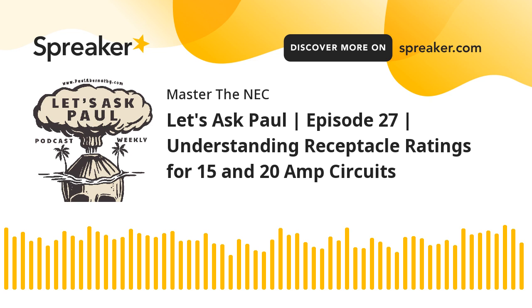So let's look at the very first one. Okay, so the very first thing we're dealing with is a 15 amp circuit breaker. Okay, it could be a fuse, but we'll say probably more modern homes are dealing in circuit breakers. So it's a 15 amp circuit breaker. What can I put on that 15 amp circuit breaker? What's the rating of the devices? The devices being a receptacle, can I put on that 15 amp circuit breaker? So let's cover duplexes first. So on a 15 amp breaker, I can put a 15 amp rated receptacle. Okay, makes sense? Obviously, it's a 15 amp rated circuit breaker, it's a 15 amp rated receptacle. Everything's fine. Good to go.